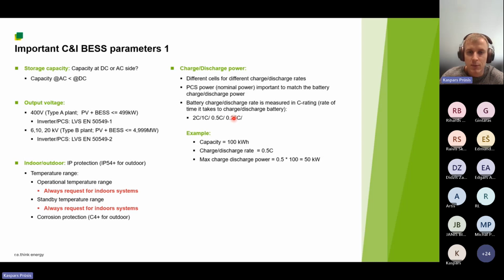And by knowing these parameters, we can also easily calculate what is the maximum output power of the battery itself if we know the battery's capacity. So for example, if we have the battery of capacity of 100 kilowatt hours, and we know that charge discharge rate is given 0.5C, then the max charge discharge power is 50 kilowatts. So we can use that to calculate this parameter.